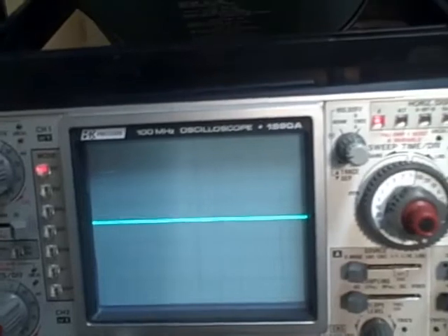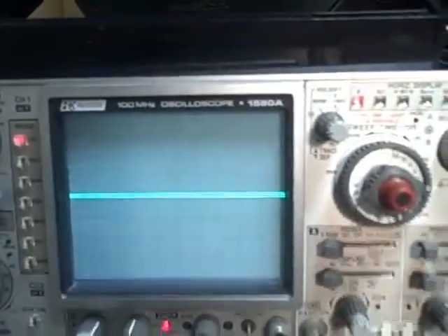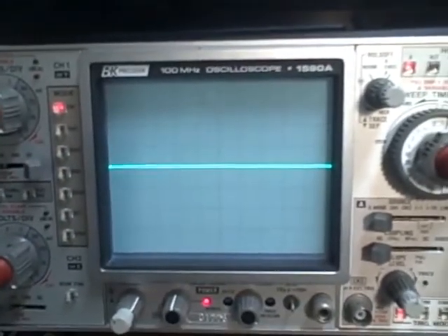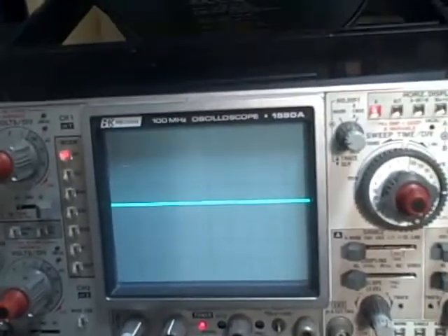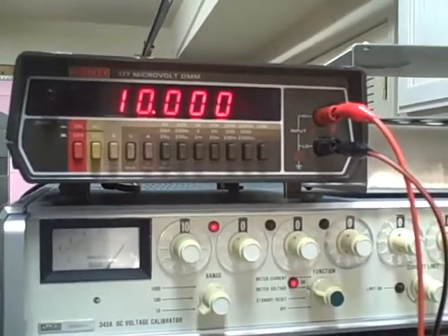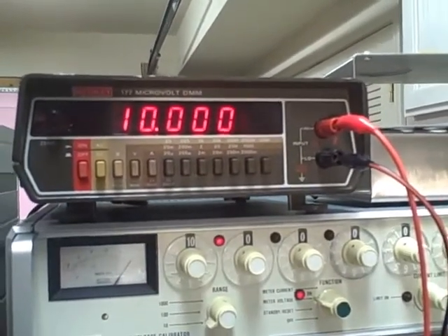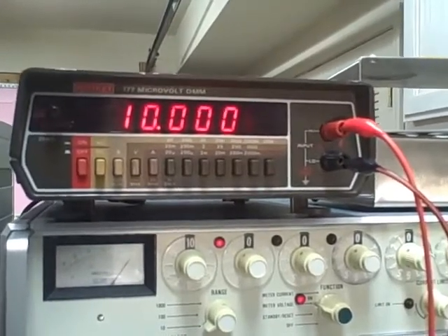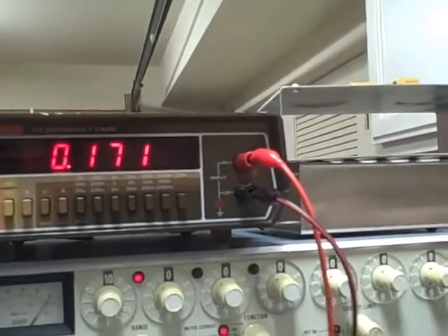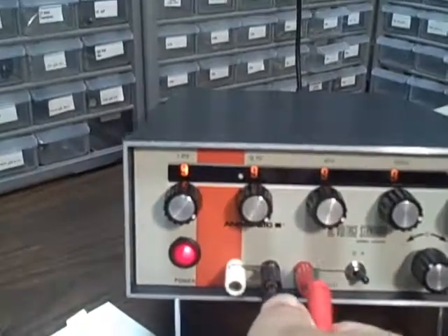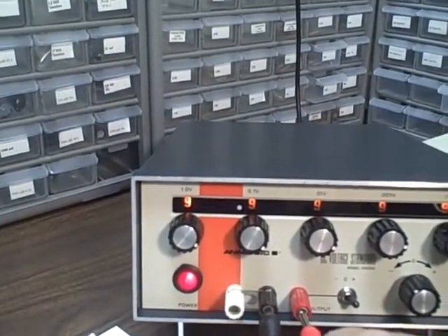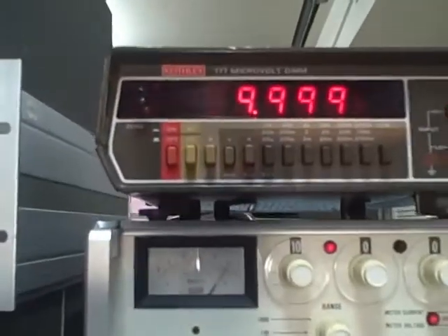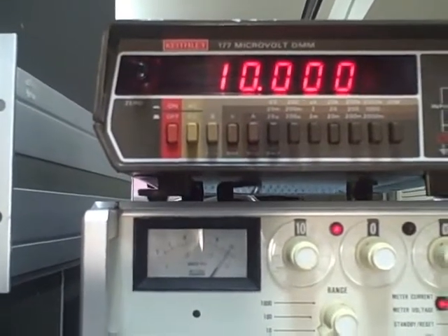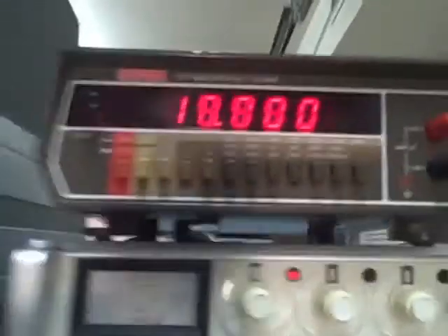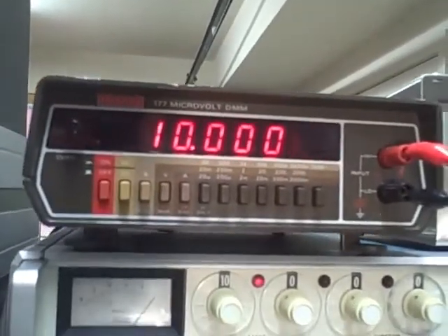Okay, we're going to go ahead and switch to using a digital voltmeter so that you can observe the voltage readings. Now that we've seen the cleanliness of the signal, that's really the majority of the reason why you'd look at it on the scope. We have the output of the Fluke 343A DC voltage calibrator at 10 volts, going into our Keithley 177, and we show 10.000, so 10 to the millivolt. Now let's transfer our leads from the Fluke to the Analogic, which is also set right now to 9.9999, or 10 volts. And we are reading 9.999, or 10 volts. So we are right there. The Fluke and the Analogic were outputting 10 volts to the millivolt.